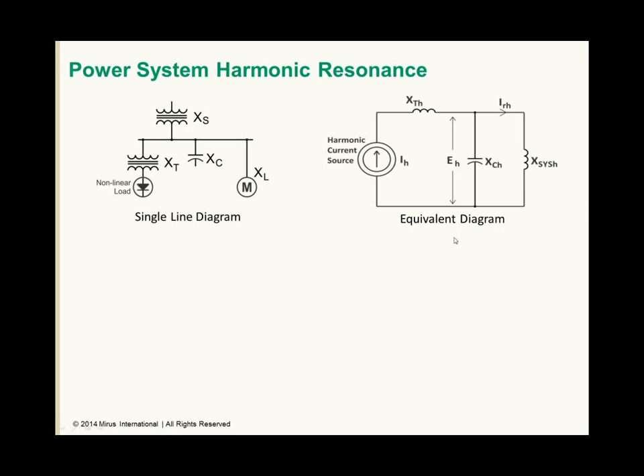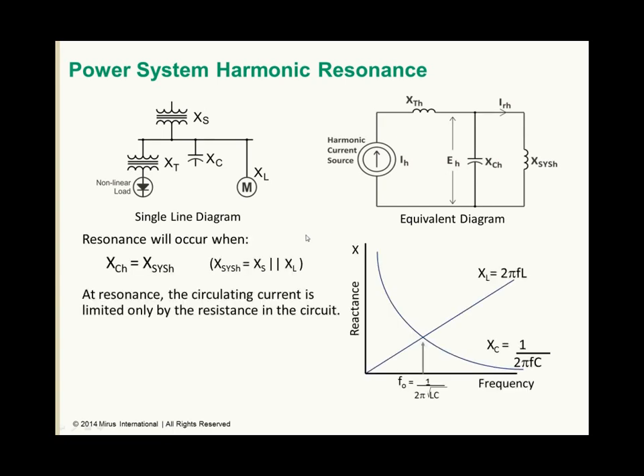The equivalent diagram of this one line is shown here, where we've got our current source of harmonics, which is the variable speed drive injecting harmonics into the power system, passing through the transformer's impedance in series, and then reaching a parallel combination of the reactive power of the power factor correction capacitors and the resultant reactance of the power system. And that would be the combined parallel reactance of the source and other loads on the power system. Very difficult to calculate in a lot of cases, but it is almost always inductive. We resonate when the reactive power of the power factor correction capacitors at a certain harmonic is equal to the inductive reactive power of the system at that harmonic.